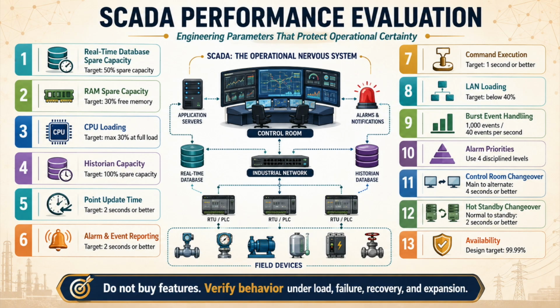During event storms, the system must preserve timestamp integrity, event sequence, alarm priority, acknowledgement status, shelving status, operator comments, audit trail, and historian event journal consistency. Poor burst handling causes delayed alarms, duplicate events, missing events, frozen alarm pages, operator overload, weak incident reconstruction, and confused decision-making during exactly the period when clarity matters most.